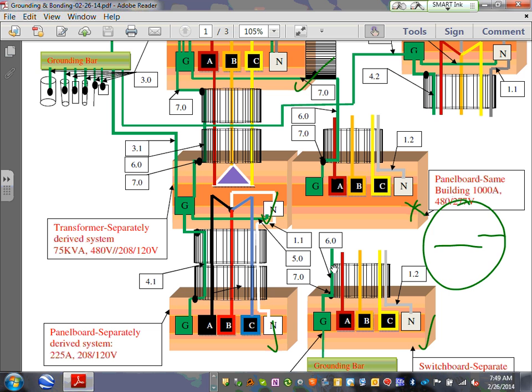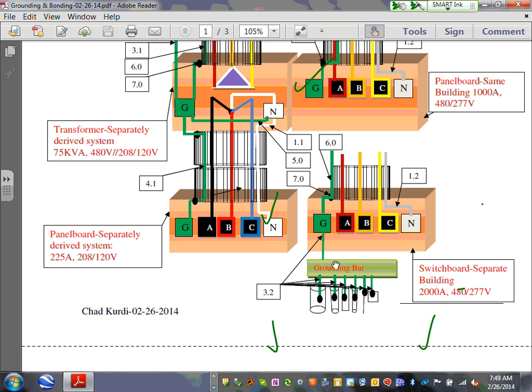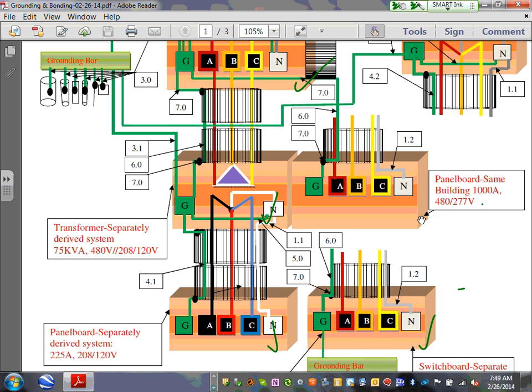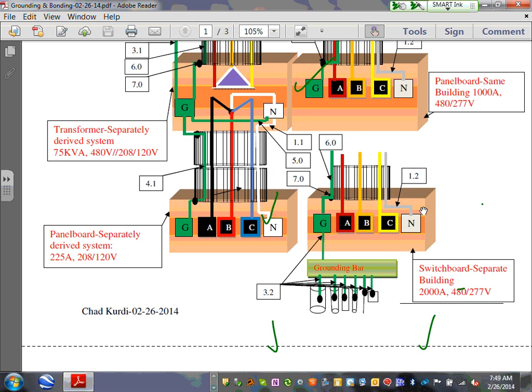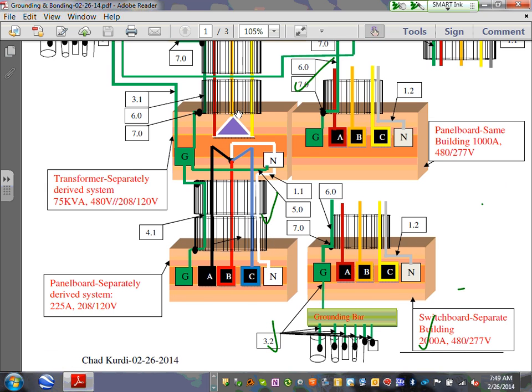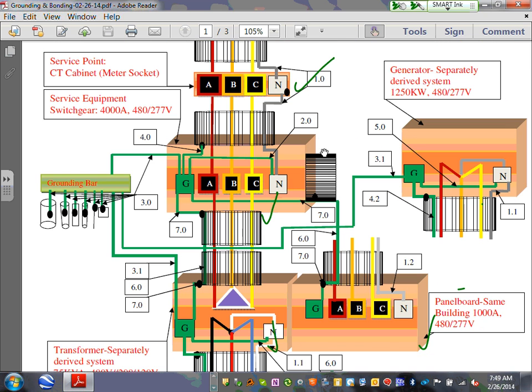Two panels. One of them is inside the building, and the other one is outside, in a different building. Can you guys see that? So this panel is 1,000 amp, 480/277, inside the building. The second one right underneath it, Karen, is a switchboard in a separate building, 2,000 amp, 480/277. Three feeders, ladies and gentlemen. One feeds a sub panel in the same building, the other feeds a sub panel in a different building, and the third one feeds a transformer that feeds a receptacle panel in the same building too.